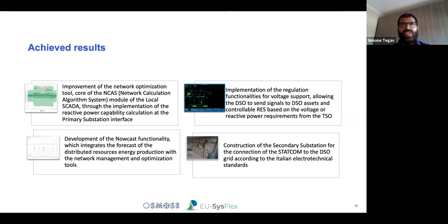Naturally, considering that the TSO is not a real partner of the Italian demonstrator team, we needed to develop an automated coordination process using an IEC 60870-5-104 protocol simulator. We implemented a protocol simulator based on the same protocol used in the real interface between the SCADAs of E-Distribuzione and Terna.